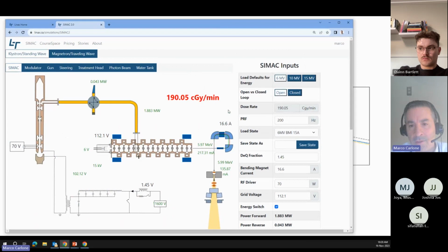So what they're doing in this case is they're varying the bending magnet current that we have over here. And as we change the bending magnet current, because the bending magnet acts like a spectrometer, it allows a different energy to go through and strike the target. So in the 6 MV mode that we've defaulted to over here, the Linac is making a 6 MV beam, and the bending magnet is configured to allow a 6 MV beam to strike it, and so this is balanced. However, it's possible for this to become unbalanced.